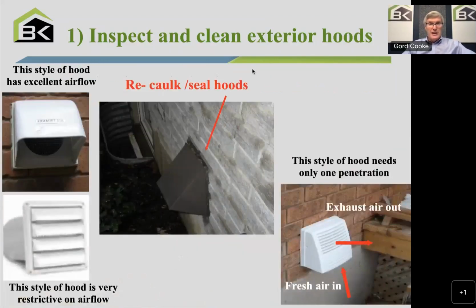So that's pretty useful. And then there are different styles of hood. I'll just remind you, the one on the top left is probably the best of the hoods. That nice rounded hood with lots of availability for air. Still has a screen on it, so you've got to check that screen. The bottom left, these are very common hoods, but they're very restrictive on airflow, and they're actually harder to clean. So in new buildings, you'd want to use a hood like the one on the top left. In older units that are installed, if they're using the hoods with the little louvers at the bottom left, you'd want to make sure those are regularly checked, and you probably need a toothbrush to clean those out.